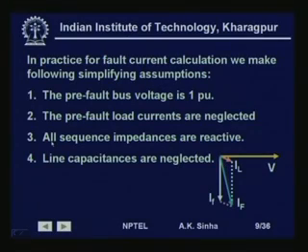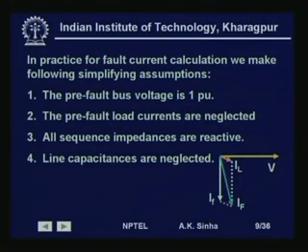Another assumption is that all sequence impedances are reactive. For most power system equipment, reactance is much larger than resistance, so the resistance value is neglected. Also, line capacitances are neglected, because line capacitances draw charging current which is much smaller than even the load current. Therefore, its effect is negligible when fault current flows, and we can neglect line capacitances.